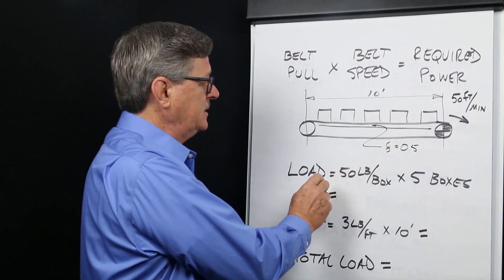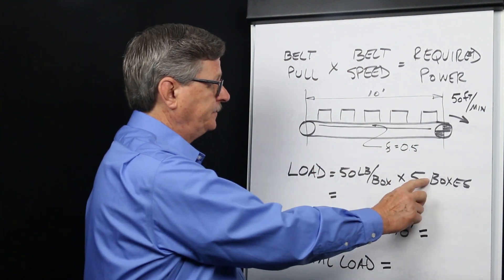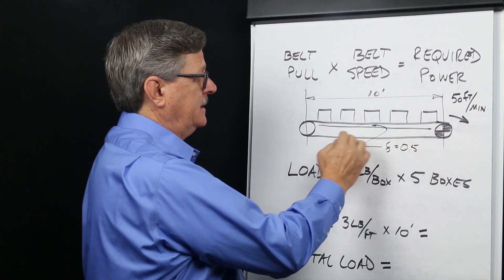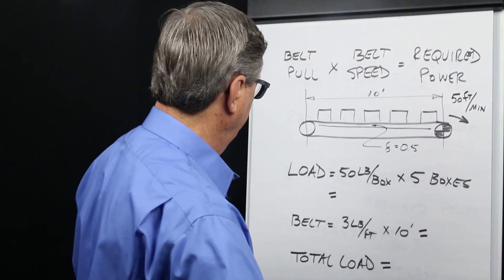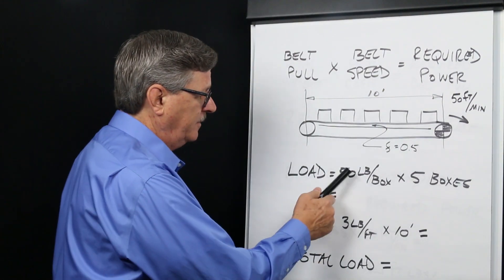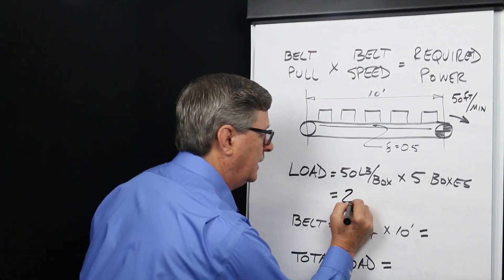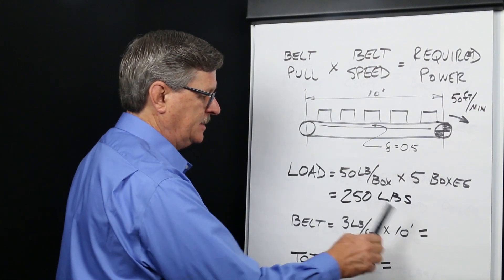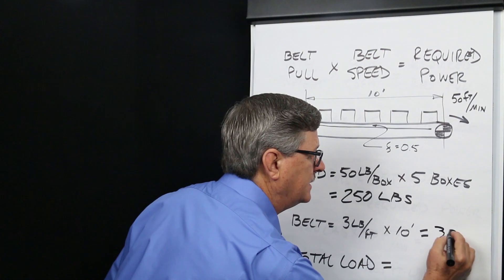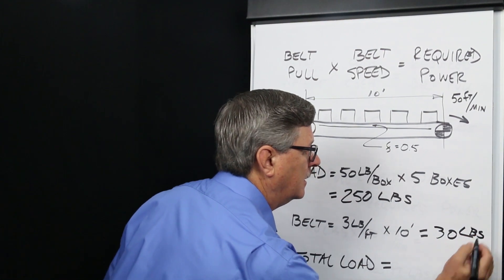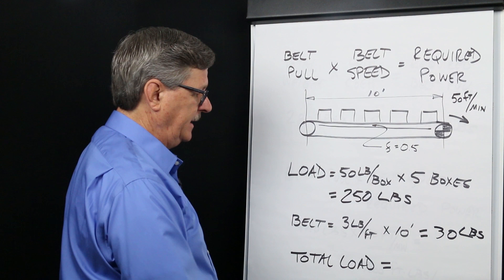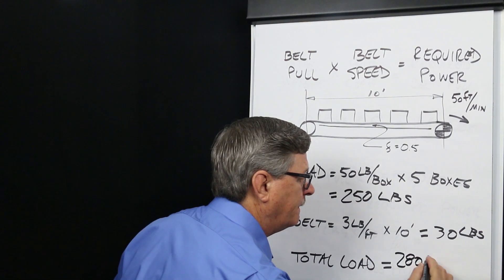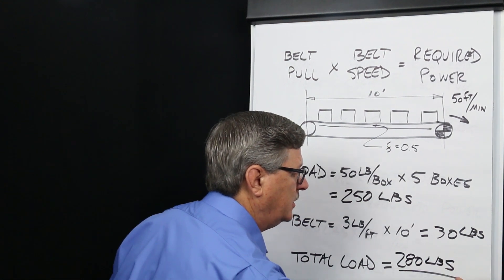Five packages at 50 pounds per package, plus the weight of the belt — which is 10 feet on the slider bed times 3 pounds per foot. 50 pounds per box times 5 boxes is 250 pounds. 3 pounds per foot of belt times 10 feet of belt equals 30 pounds. The total load on the slider bed is 250 pounds plus 30 pounds, or 280 pounds.